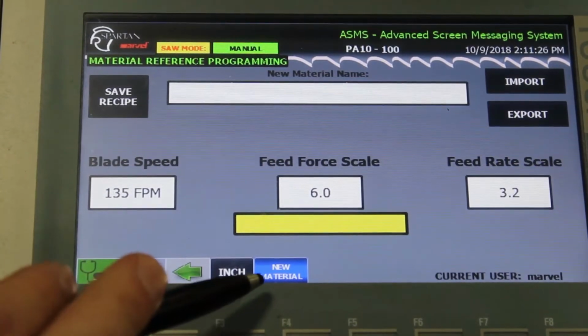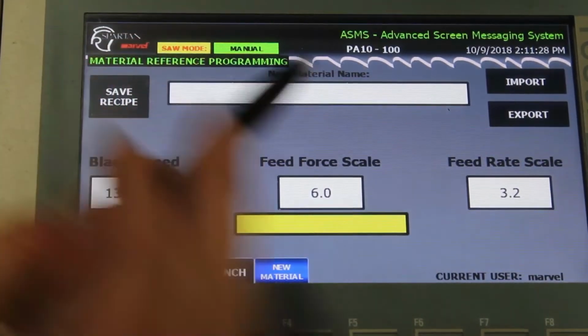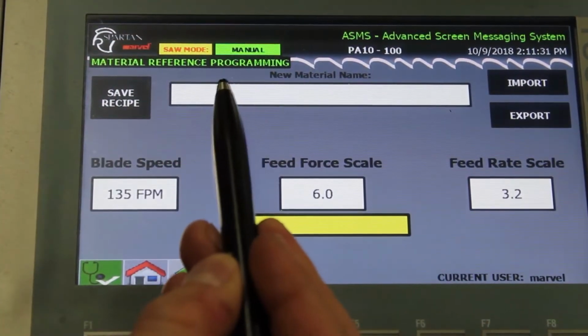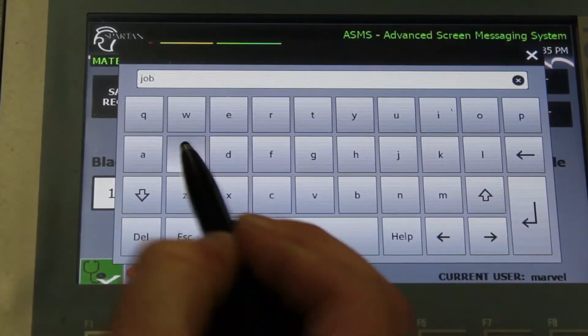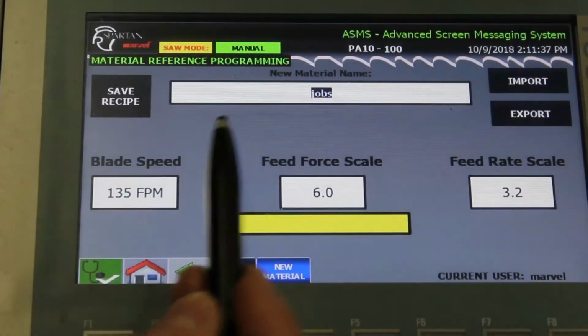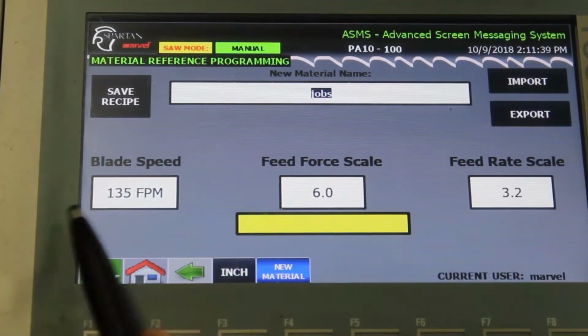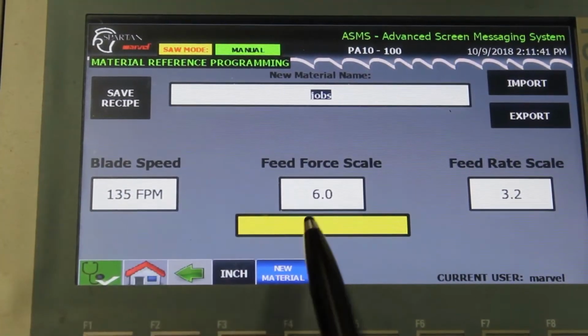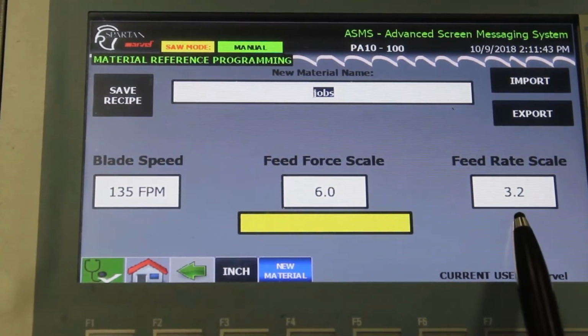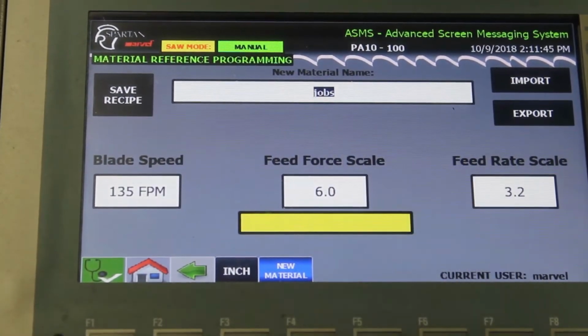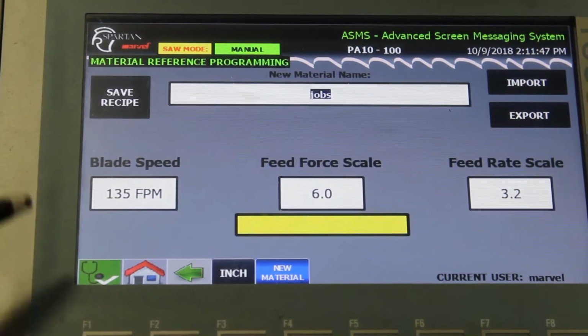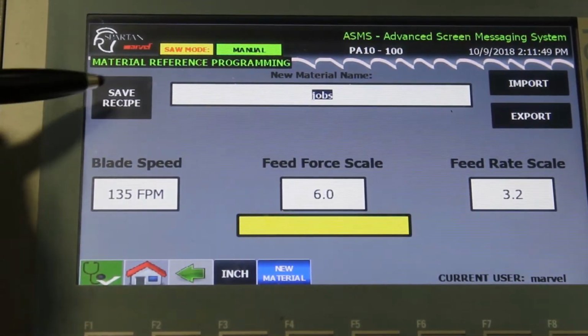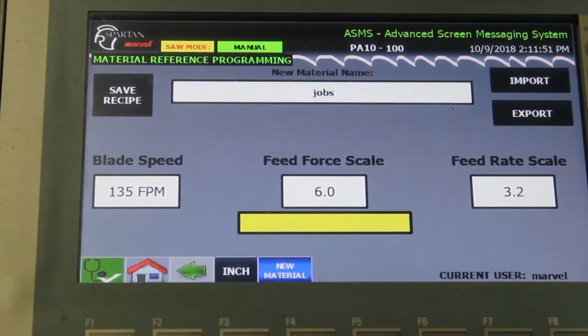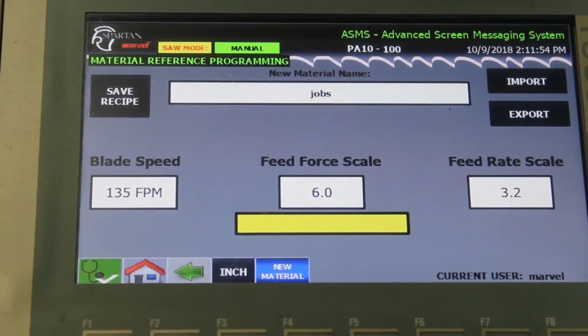When in new material mode, you'll see that the new material name area is blank. When pressed on, you can type in the name of your new material, and it will display. Again, you can set the blade speed, feed force scale, and feed rate scale for this material. Once you've completed entering all your desired values, press the Save Recipe button, which will save this material into the system.